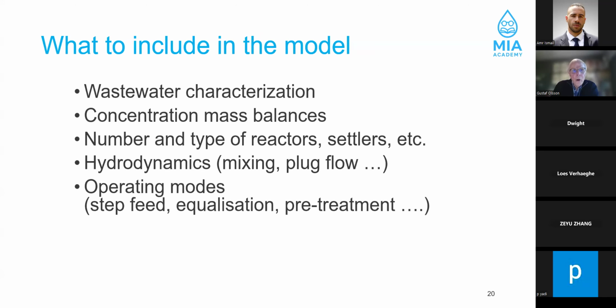And then, of course, the operating modes. Are we operating in step feed? Is there an equalization basin? Is there any pre-treatment? And so on and so forth. And of course, sensor and actuator dynamics. In other words, how long does it take to know the change of substrate, for example, or the oxygen uptake rate and so on? How long does it take when I give an order to an actuator, a pump or a compressor, whatever it is, to really make a change?